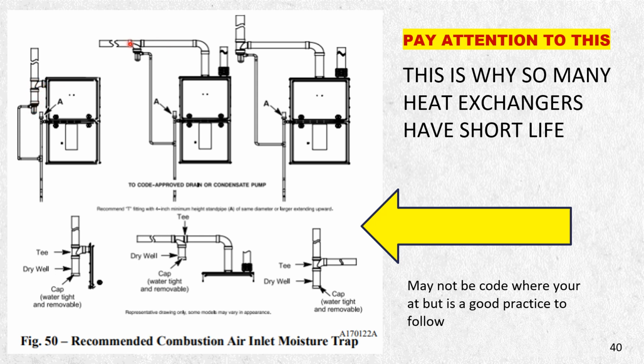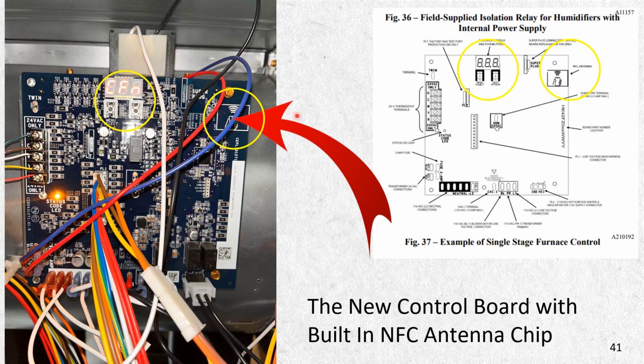Here you've got a sediment trap there, and you've got a sediment trap in a few places, but it's kind of a good thing. It may not be by your code, but it's a good practice to follow. And it will cause a short life to your heat exchanger if you don't get that moisture out.